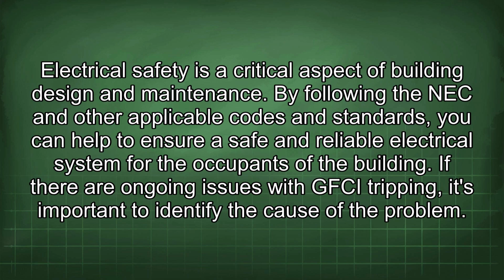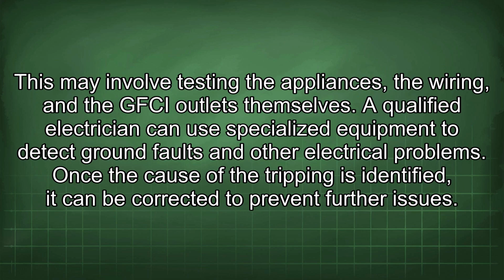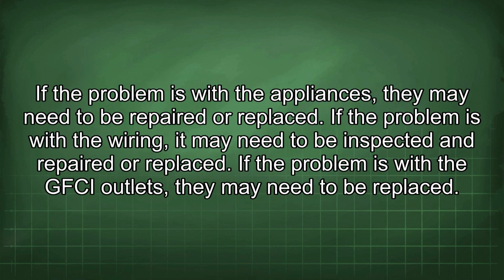If there are ongoing issues with GFCI tripping, it's important to identify the cause of the problem. This may involve testing the appliances, the wiring, and the GFCI outlets themselves. A qualified electrician can use specialized equipment to detect ground faults and other electrical problems. Once the cause of the tripping is identified, it can be corrected to prevent further issues. If the problem is with the appliances, they may need to be repaired or replaced. If the problem is with the wiring, it may need to be inspected and repaired or replaced. If the problem is with the GFCI outlets, they may need to be replaced.